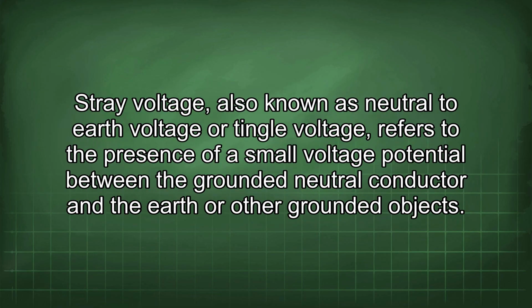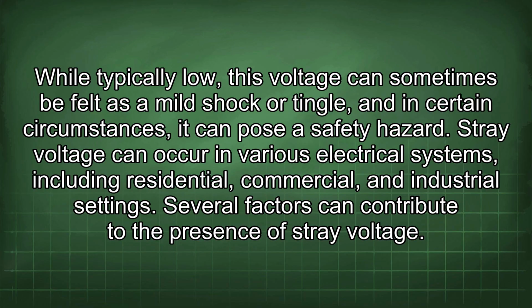Stray voltage, also known as neutral to earth voltage or tingle voltage, refers to the presence of a small voltage potential between the grounded neutral conductor and the earth or other grounded objects. While typically low, this voltage can sometimes be felt as a mild shock or tingle, and in certain circumstances, it can pose a safety hazard. Stray voltage can occur in various electrical systems, including residential, commercial, and industrial settings.